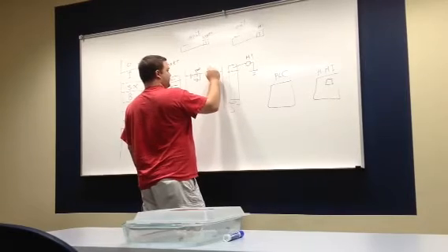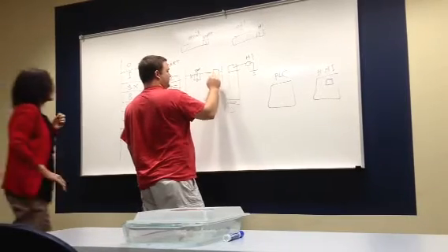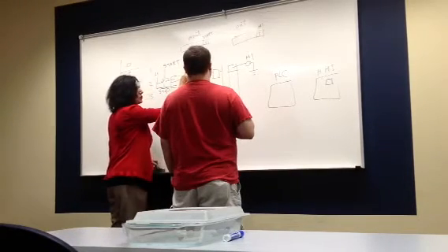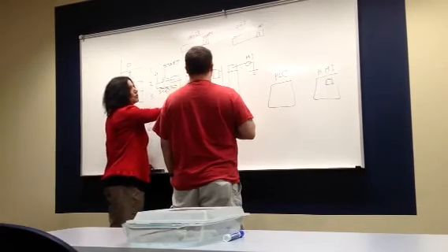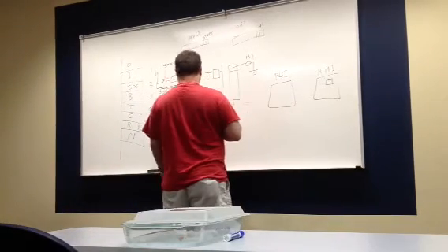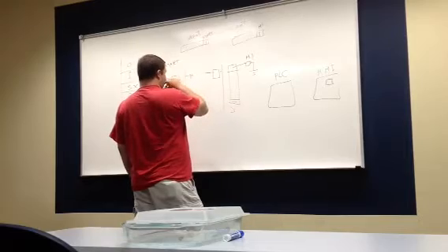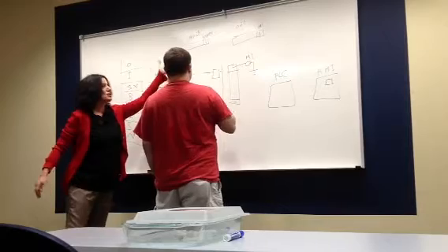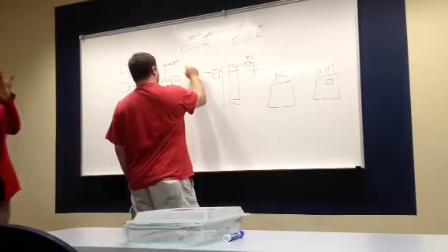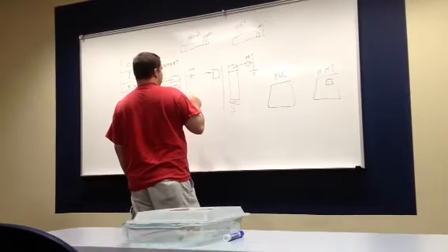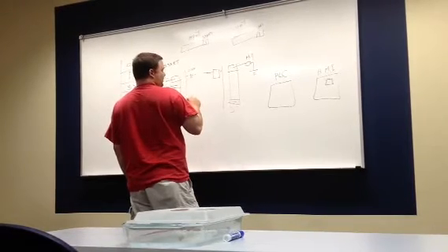I think we got it. No start, no stop. If the output is true for the motor output and you do not receive the input after 5 seconds, so somewhere else someone started the motor, O colon 2/0, for example. If the motor is running and you don't receive the input in 5 seconds, send an alarm. It doesn't matter to flash, just any bit to tell you about it.